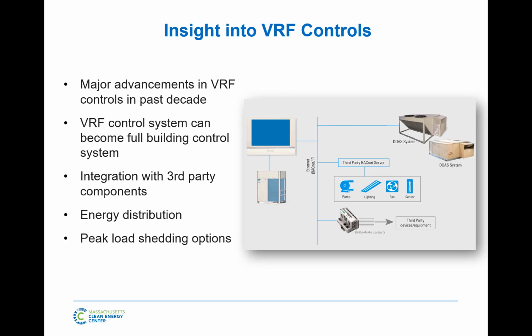Go ahead. So it all depends on what you are doing on the building side. For us on the VRF side, all we have is a terminal. The terminal says you close that contact, and I'm going to maximize my use to 40% or 50% or 60%. What you use to enable that contact is up to you. Whether you just want to do it manually, whether you got something that's tied into the time of use electricity by the grid, whether your generator output, whatever it might be. What we provide is that contact that says you can tell me if you want me to peak shed on peak or to limit my energy use. Yeah, it's all in the software, correct.